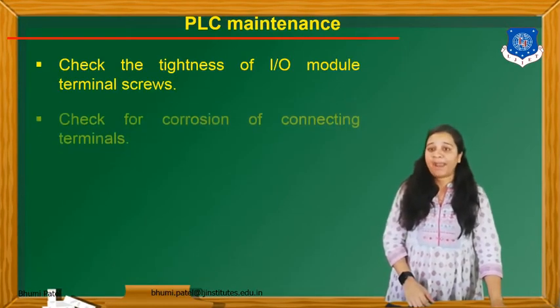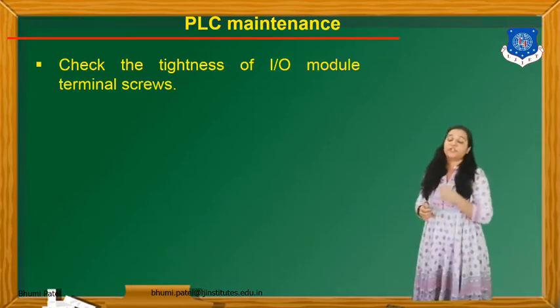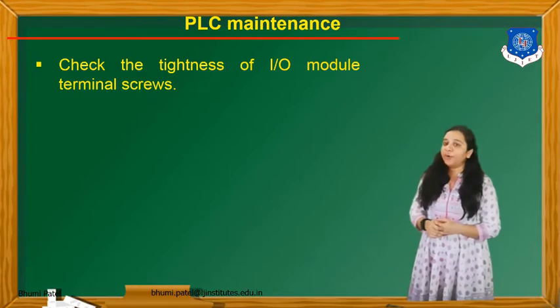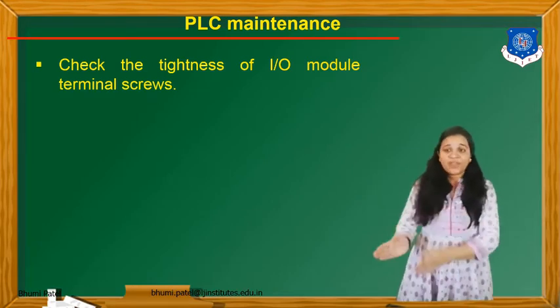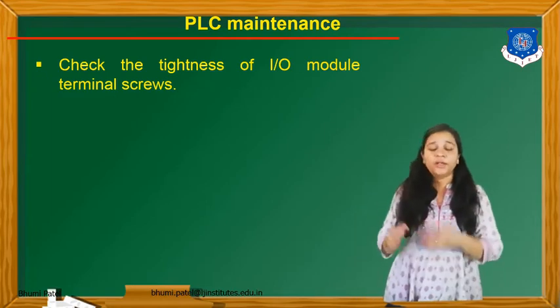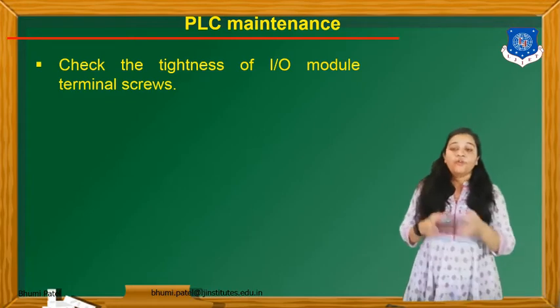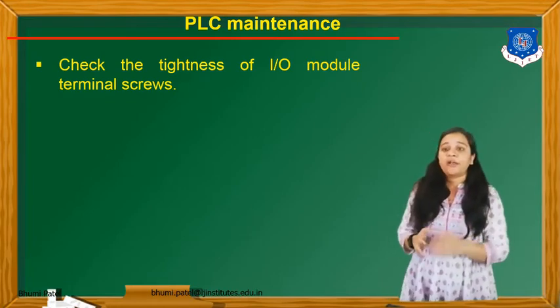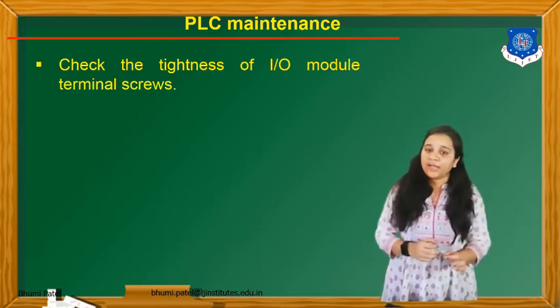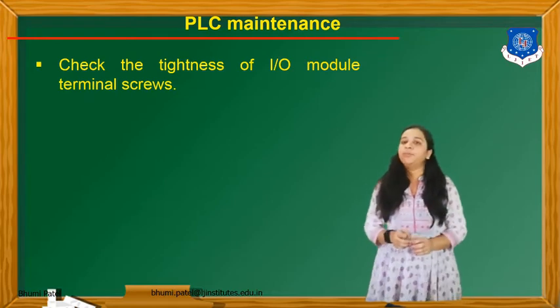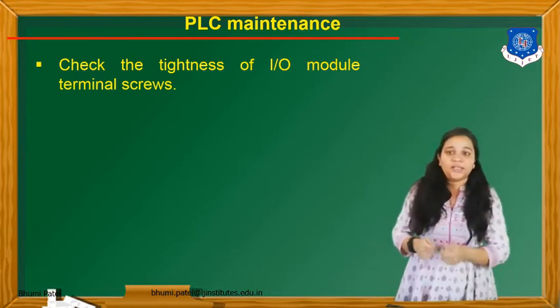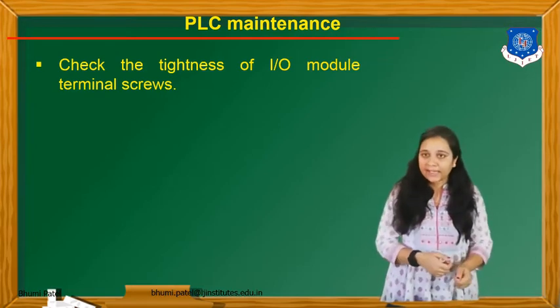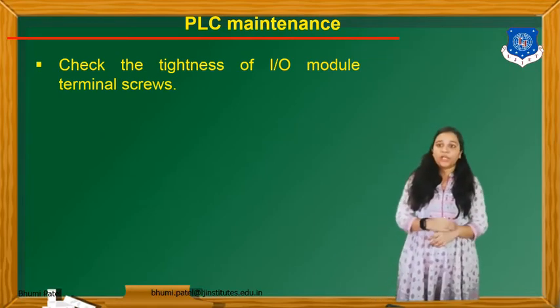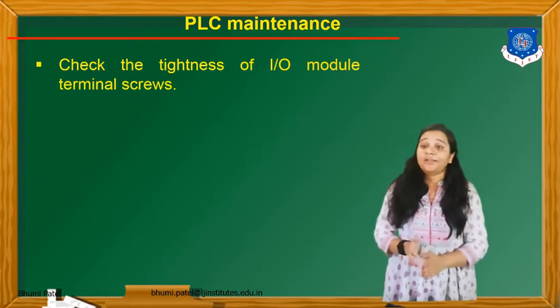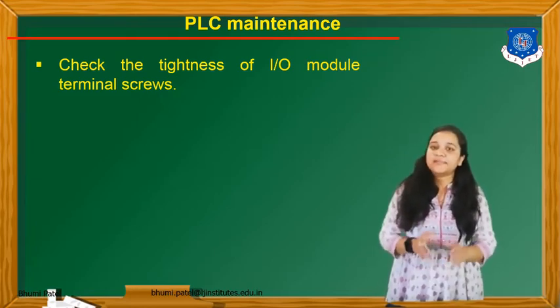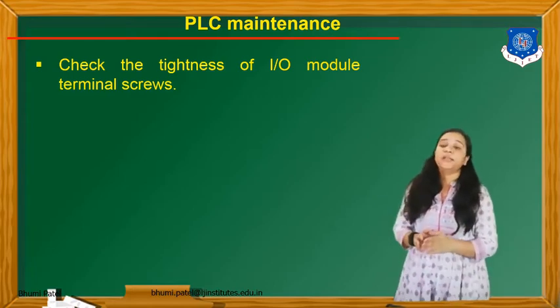So first, PLC maintenance. We have to check the tightness of the IO module terminal screws. When programming is done, we can connect different analog inputs and outputs for the PLC hardware. For example, we can connect a push button switch as an input on/off switch, connecting its positive and negative terminals with the PLC hardware. So first we check the tightness of the input as well as output modules connected with the PLC hardware.